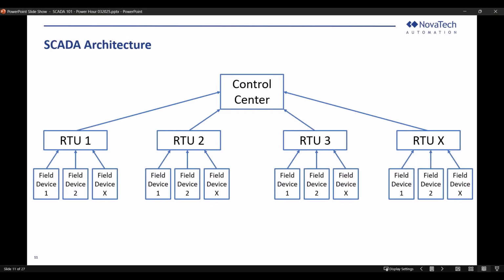And then the RTU does protocol conversion. So if data coming in to the RTU is Modbus, it can convert that data to your control center using DNP3 or other protocols. Usually this is what we see. Obviously it can be different in other applications, which we'll go through in a bit. But at the end of the day, most data goes to the control center. Again, depending on your company standard, not all data goes to the control center. The RTU can parse out the critical data and then send it to the control center. So maybe only 20% of the data that's in the RTU goes to the control center. It's really up to your company standard.